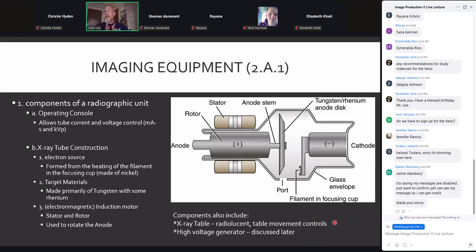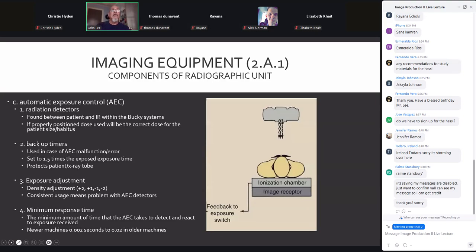Now, the high voltage generator itself is comprised of the filament transformer, the high voltage, high tension transformer, and the rectifier system. Those three systems all housed in the same metal box within the room comprise the high voltage generator. Other controls include the AEC, the automatic exposure control. Remember, the detectors are positioned between the image receptor, the grid, and the patient. So between the patient and the grid is where the detectors are.